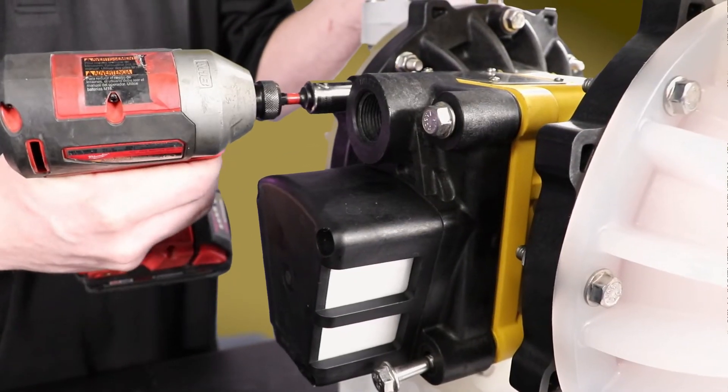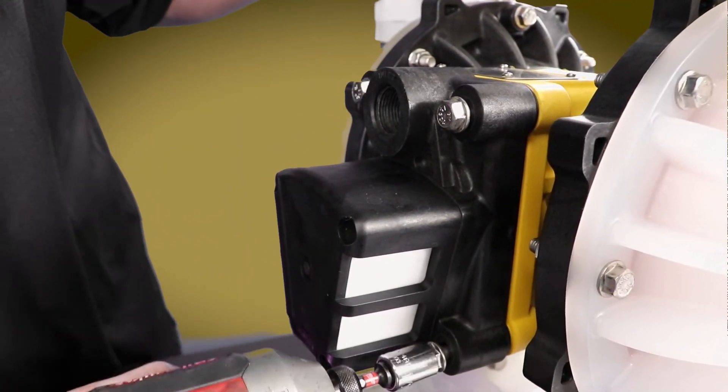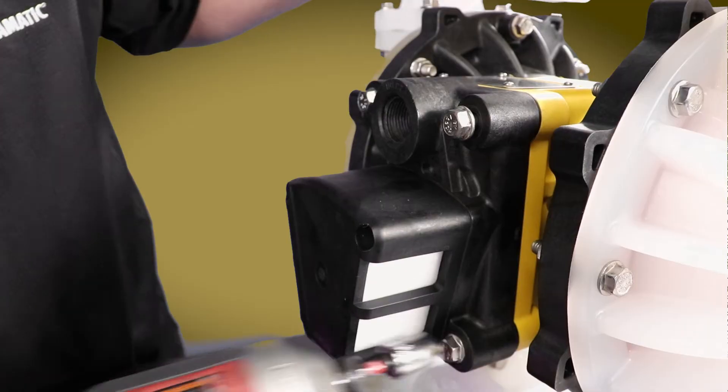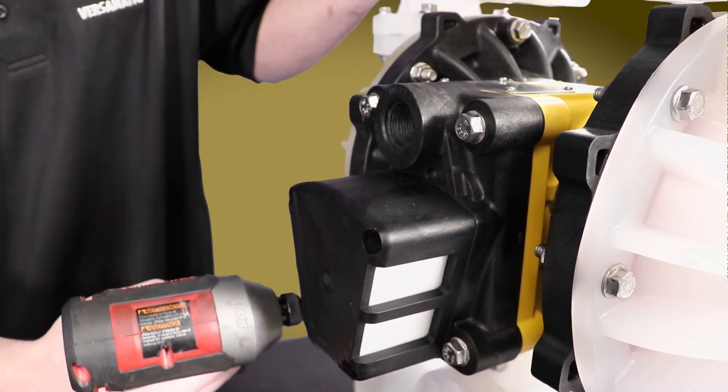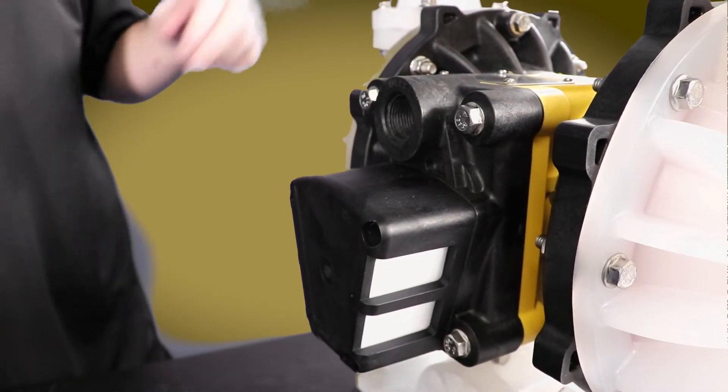Reinstall the outer gasket, air inlet cap, and reinstall the cap screws using a half inch socket to hold the air valve body securely in place. Tighten the cap screws with a half inch torque wrench to 150 inch pounds.